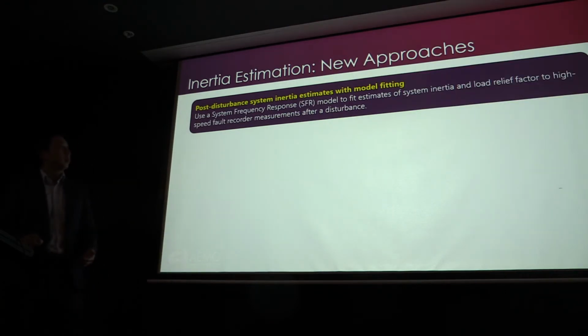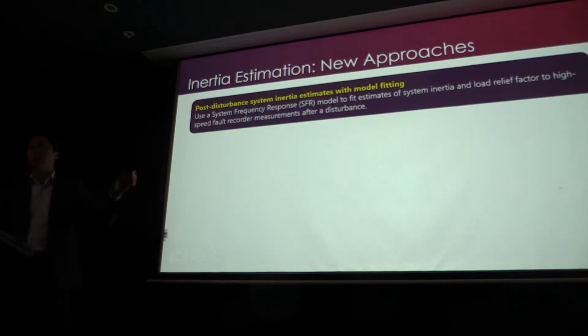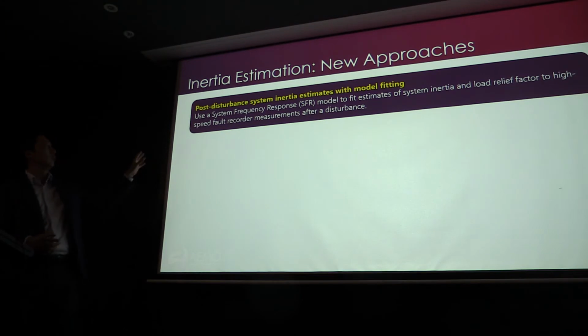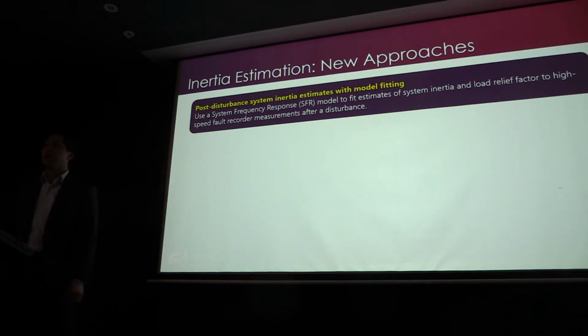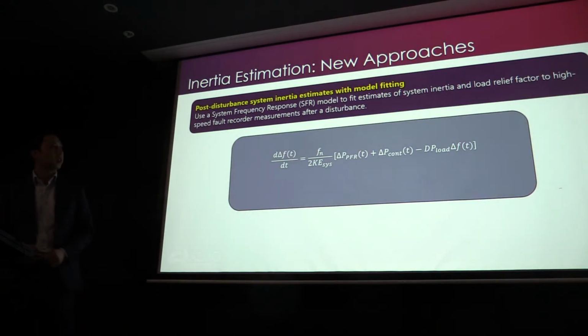So this is an approach that we've been trialing in AEMO, where rather than just using the frequency trace, we're trying to fit it to an actual model. So we have a system frequency response model, and we are trying to fit system inertia and load relief at the same time. So we get 2 for 1 here, and to the high-speed frequency recorder data. And so this is what we're trying to fit.